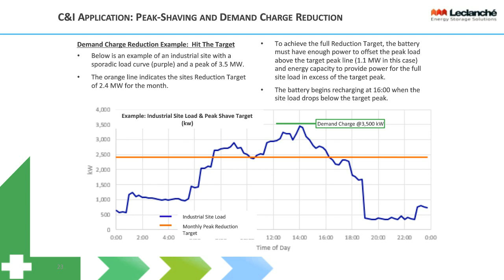So utilities will require certain levels of demand charges to compensate. Battery systems in particular are very helpful in trying to shave off those peaks, and that's been a principal objective of many commercial and industrial applications. In this case, a 3,500 kilowatt peak: you add about 1 megawatt of battery capacity, and you can reduce that peak down to 2,500 kilowatts.